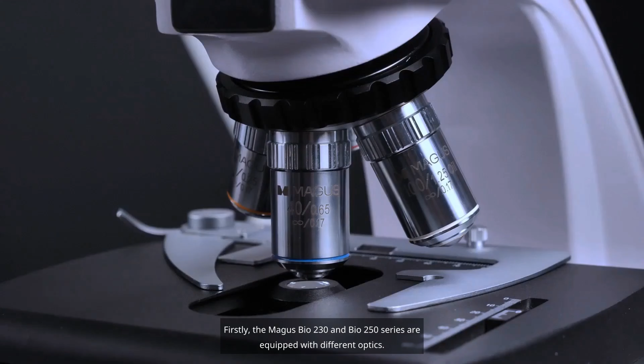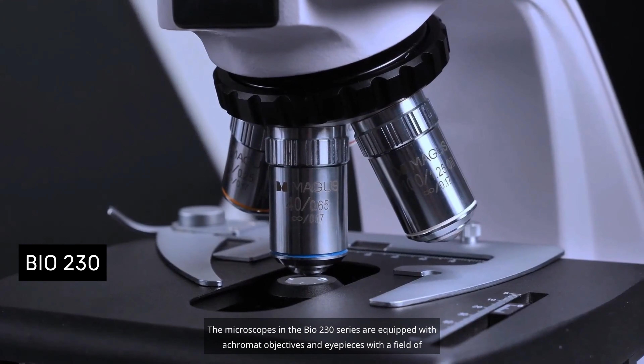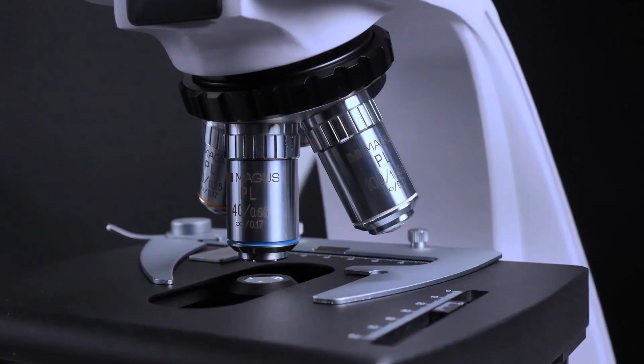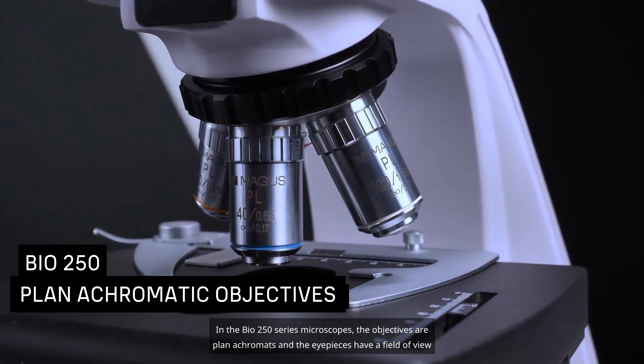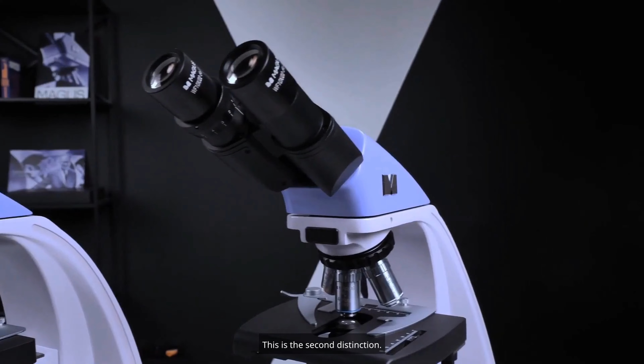Firstly, the MAGUS Bio 230 and Bio 250 series are equipped with different optics. The microscopes in the Bio 230 series are equipped with achromat objectives and eyepieces with a field of view of 18 millimeters. In the Bio 250 series microscopes, the objectives are plan achromats and the eyepieces have a field of view of 22 millimeters. This is the second distinction.